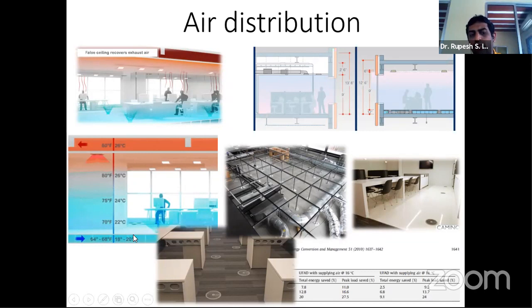And then as the height or the volume of the room rises, my temperature would increase. So my cooling zone itself need not be the full 10 feet or probably the 12 feet of space that my room would occupy, but it could be only 7 or 8 feet of space, and my exhaust temperature could be as high as 26 degrees or even 27 degrees in an underfloor system. Whereas the exhaust temperature on an overhead system would be somewhere around 25 or 25.5 degrees Celsius. So these are also picking up now. I mean, underfloor systems are now becoming more accepted in the industry. I think there were a few challenges before, but now improvements have been made, research has been conducted, and an underfloor system could go in with a ducted or a plenum kind of supply system.